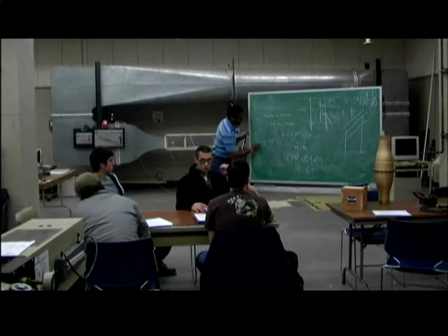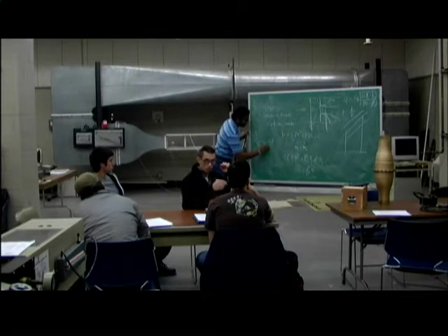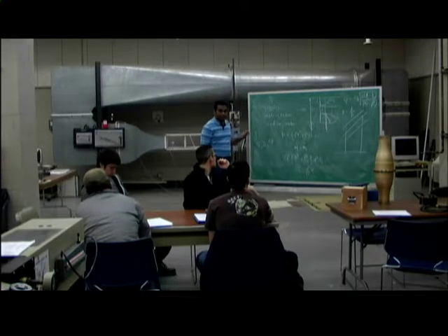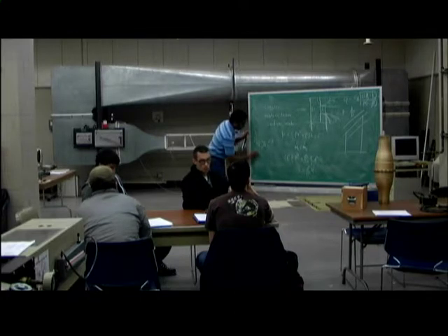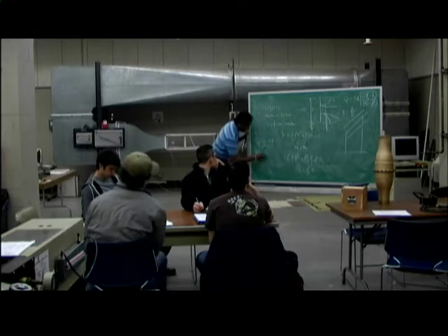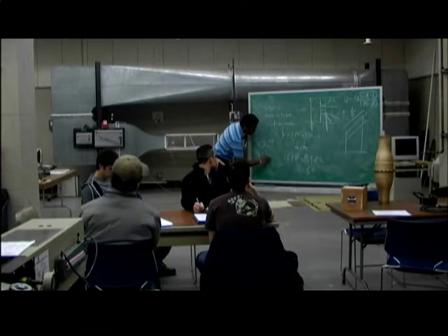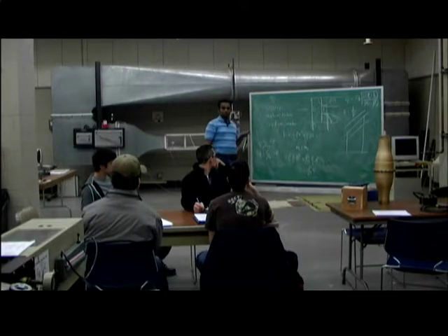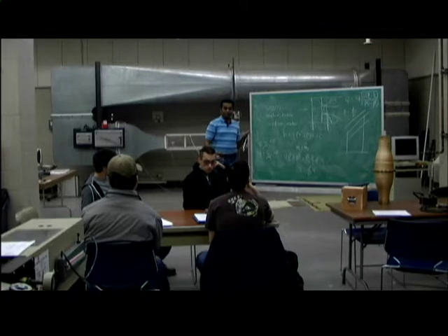Okay, let's say this is standard flow rate, and this is standard mu. What is mu? Viscosity. So viscosity changes with the temperature, right? So you need a correction. So if you say that the actual flow rate QF is equal to, again, these are geometric constants, those don't change, but your mu changes for the same delta P, for the same pressure difference, okay?